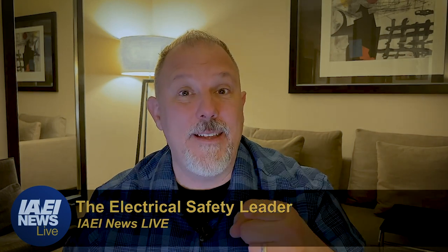And the argument there by some was, look, if I have a bad actor and the bad actor is the device, maybe the manufacturer didn't follow certain rules and regulations with regard to sourcing their components, and there's a chip on this device that has been compromised. It doesn't matter any of the cybersecurity things that you do to harden the system or protect from people engaging. You have a compromised system. And they'll give you cases where that actually happened to transformers and other equipment out there, drives that were compromised on installation. And then at a point in time, say a drive just started to accelerate the motor until it achieved a rapid disassembly in the field.